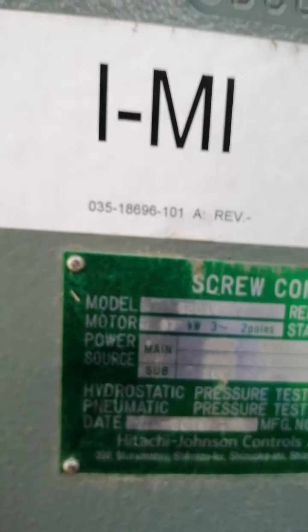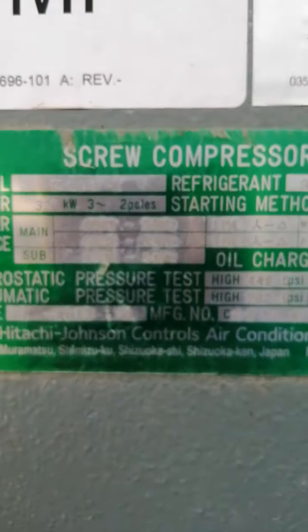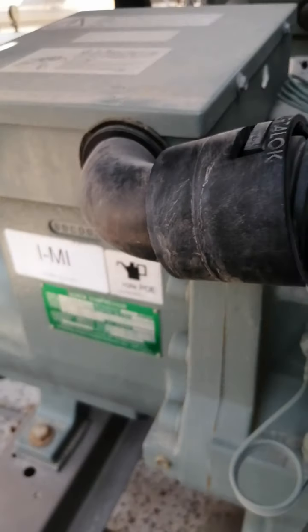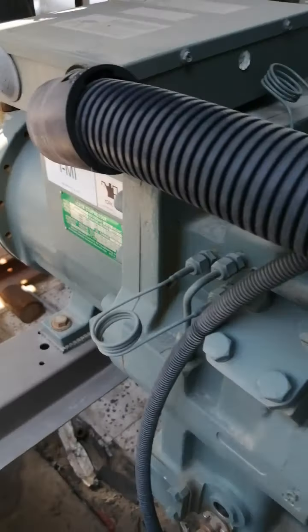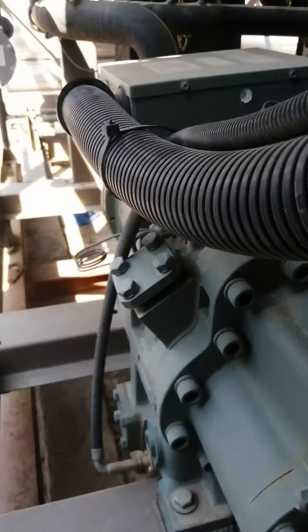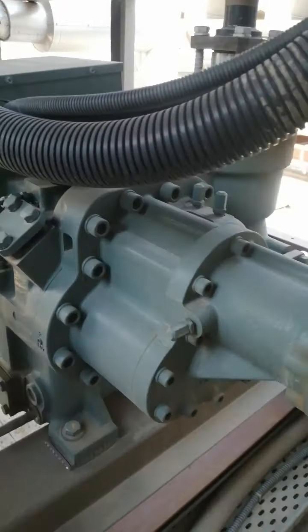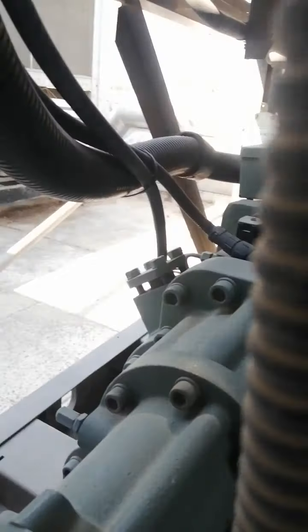Okay. Made in Germany. Okay. Refrigerant 134. Okay. It is a compressor. So you can check the Hitachi compressor. It is a 50 ton. One system compressor 50 ton and the other is also 50 ton. That is a total of 100 ton chiller, air cooled.